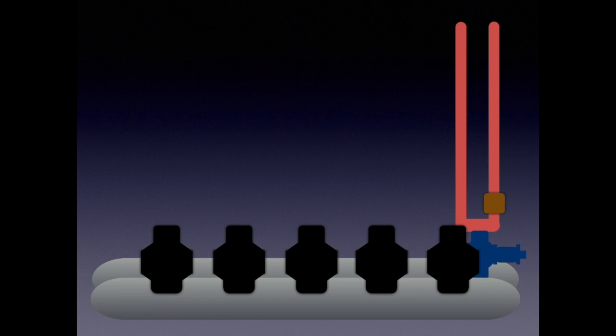These two valves essentially perform the same function as the headmaster. This hold back valve has a predetermined pressure that it needs to maintain. It's usually stamped into the body. On a 404A system this pressure will be 180 pounds. So it will hold back the refrigerant in the condenser to maintain 180 pounds of pressure.